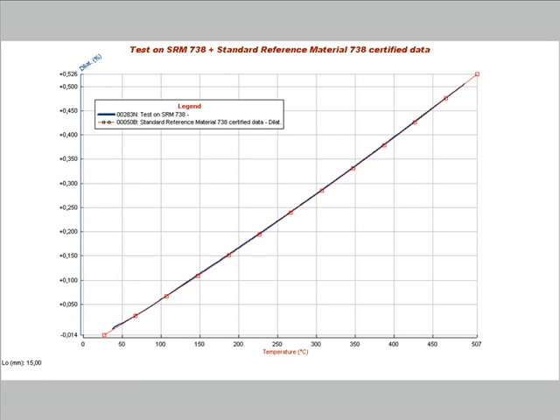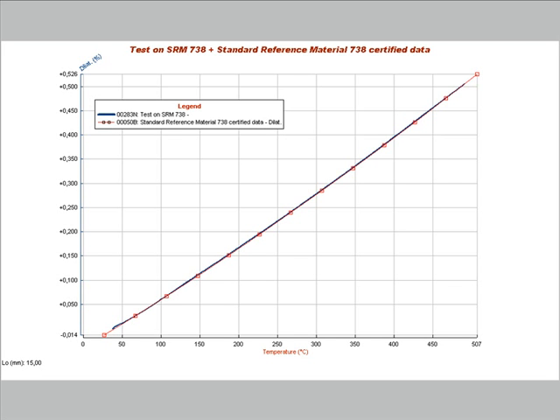The measurement carried out on both sides of the sample with no contact and with no interference from the measuring system is indeed an absolute measurement. It is not like in traditional dilatometers, where the sample is contained inside the measuring head, which is also expanding by itself. If the sample holder is made of alumina, which has a high thermal expansion coefficient, the expansion of the measuring head itself may be much bigger than the expansion of the sample under measurement.